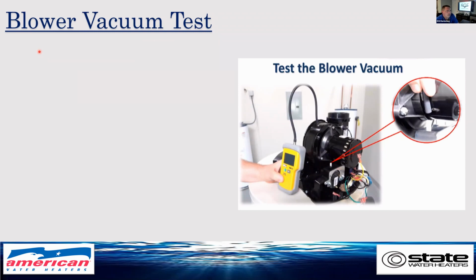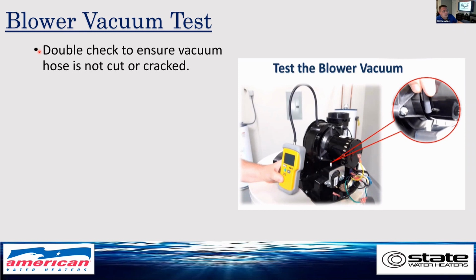So, our blower vacuum test. Double check to ensure the vacuum hoses are not cut or cracked. Run into this a lot with heaters not coming on. It's usually on new installs where they're carrying them down and they don't realize that they crack or rip or tear that hose. And lately I've had quite a few that are coming back with breaking that brass fitting off the top of this blower.